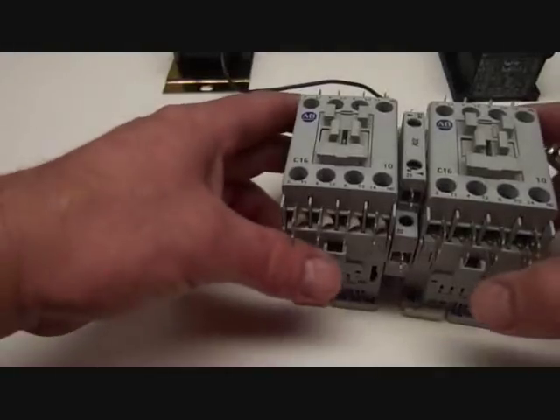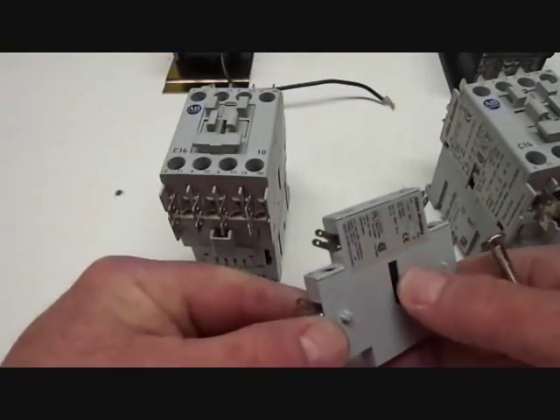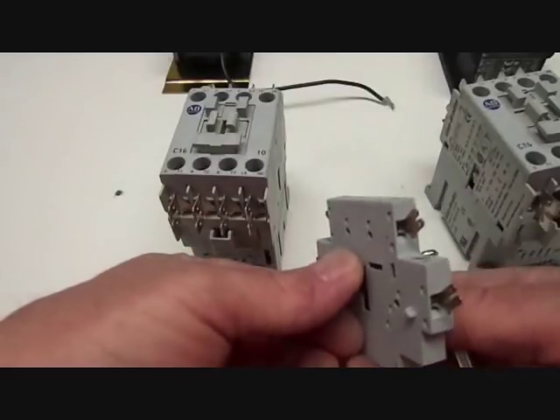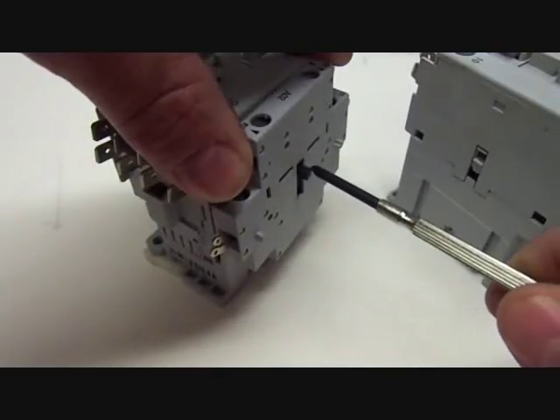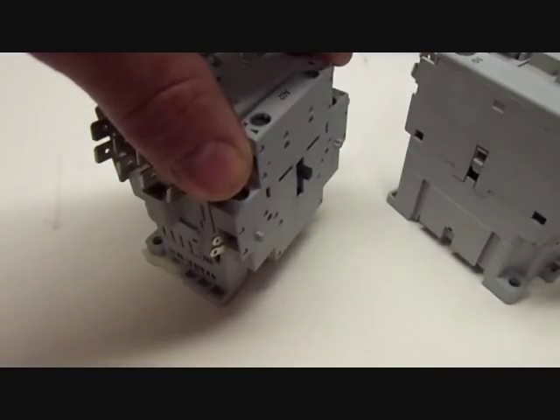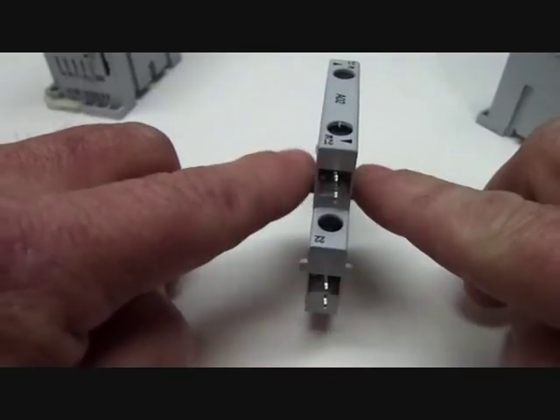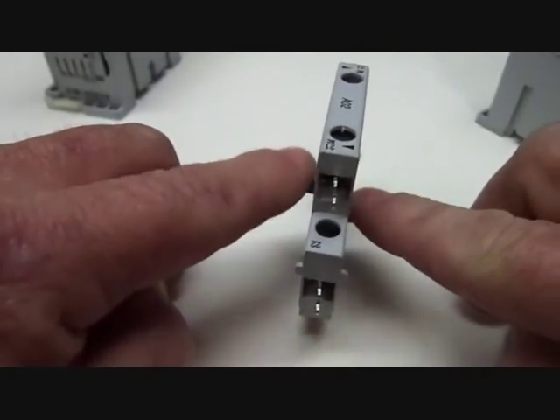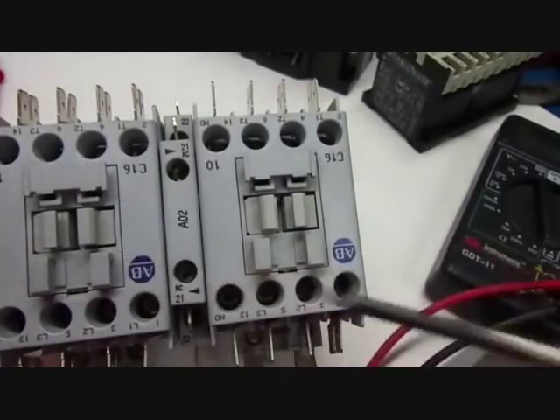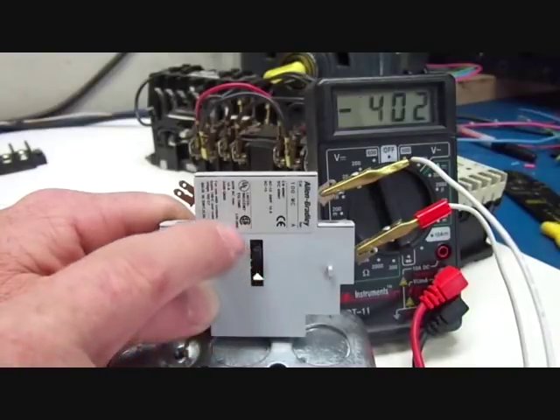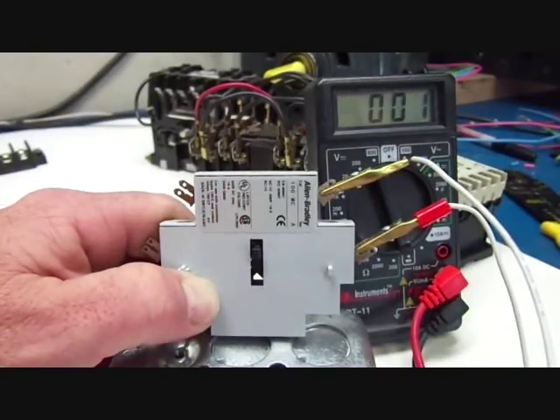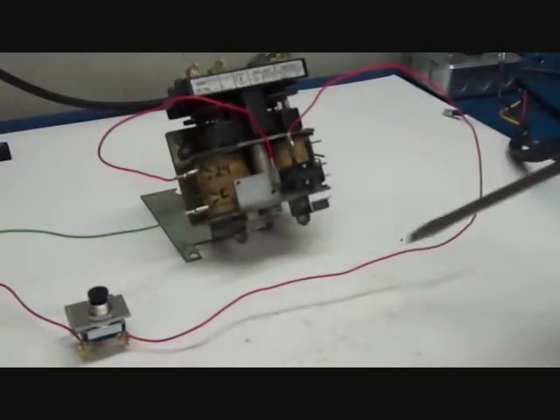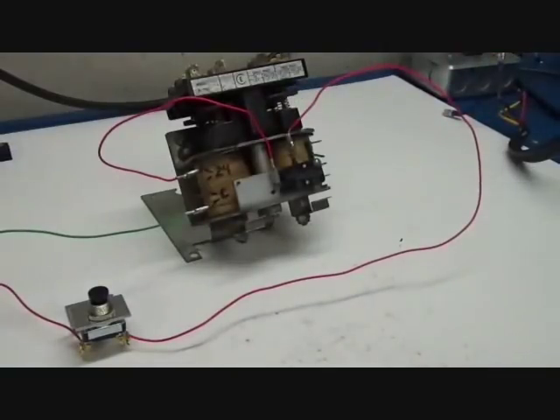Here's another identical contactor, and they're made to be joined together with this interlocking module to make one reversing contactor. The interlock device has these little tabs that can only be moved individually. The tabs fit into the contactors and physically prevent both sides from being pulled in at the same time. It also has two normally closed switches built into it that work as the electrical interlocks, one for each side. So just like on the old contactor, you would run one of the 24 volt coil leads through the appropriate interlock switch and then to the coil.